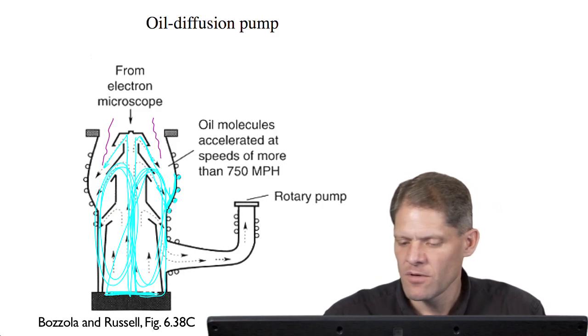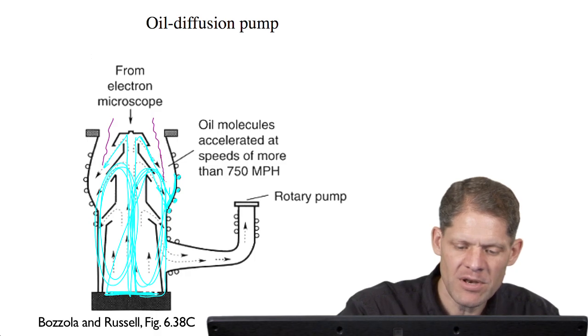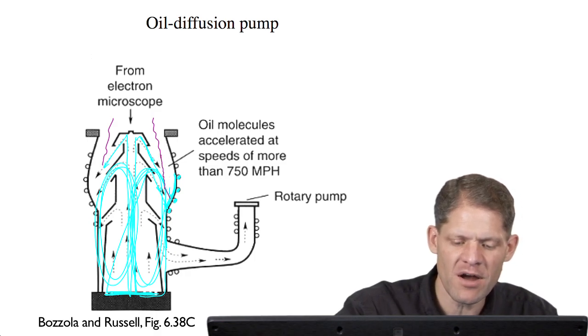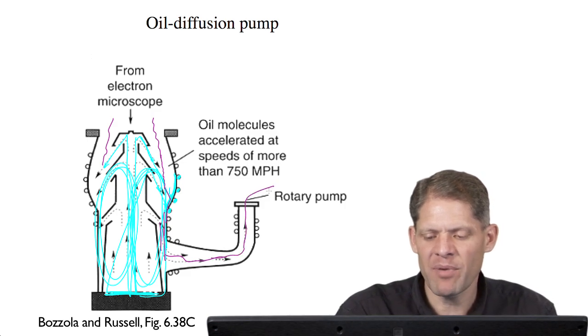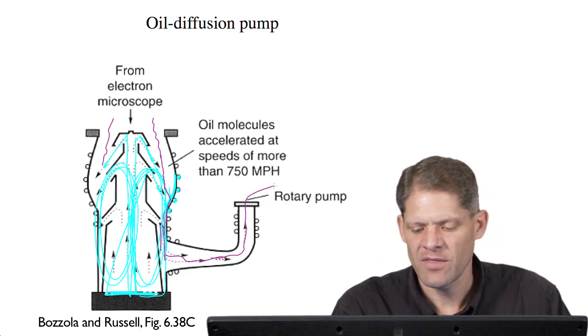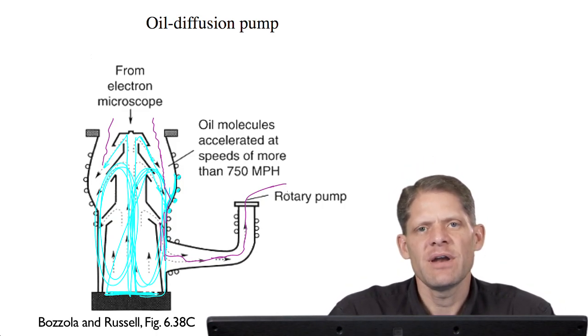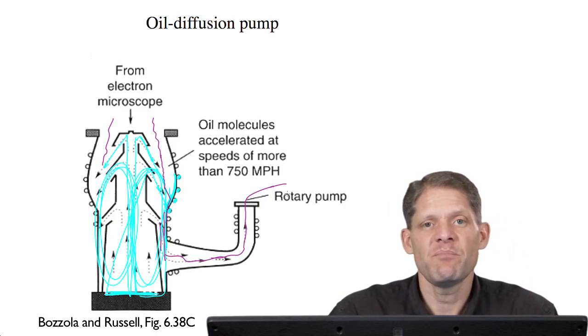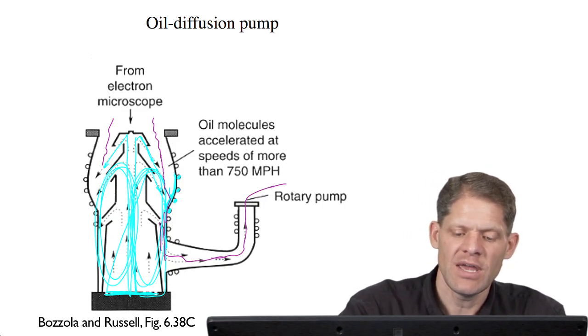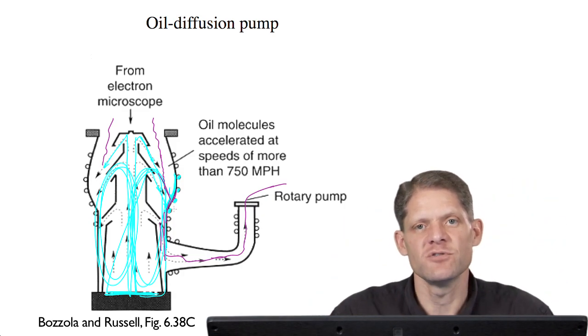And as gas molecules from the column come in here, they're hit by oil molecules and knocked down into the oil and pushed down further and further in through the pump. And eventually they escape and are exhausted and are passed to a holding tank that is pumped by the rotary pump. Now the oil diffusion pump is quieter. But every once in a while at the electron microscope, you can hear a little pinging sound. And that pinging sound can be oil molecules hitting the sides of the oil diffusion pump as they carry gas molecules down and away.